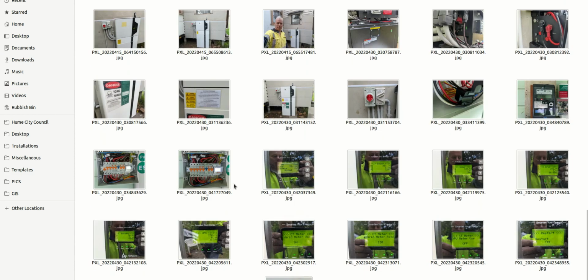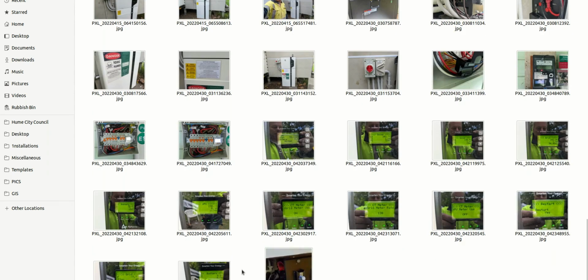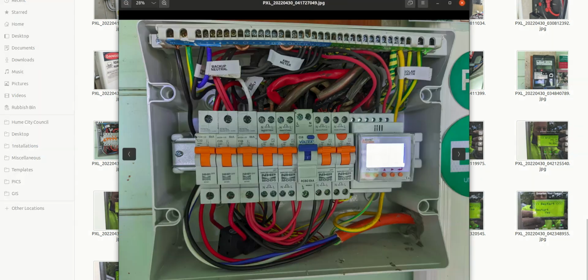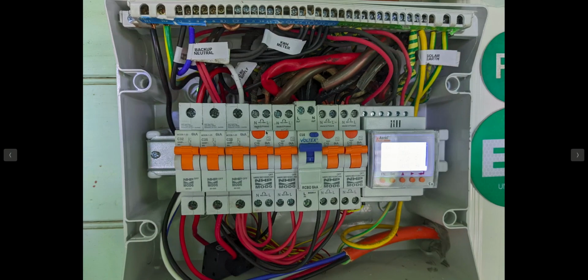So back where we started, the Alpha ESS doesn't join the neutral and earth together when the grid goes off and it goes into backup mode. So where's the final determination? I can't say final solution. The final determination is here, which is everything's joined in the one neutral bar, nice and easy, easy peasy. There, as you can see, this is the arrangement for the Alpha ESS, the way they organise this meter. It's got multiples of terminals being used for the voltage reference.